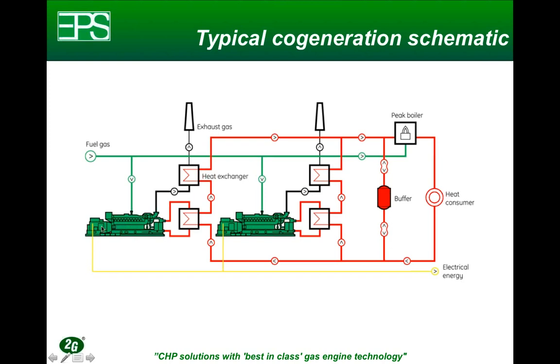Then when the engine is producing power, it will also produce heat, and it will have a few circuits on the engine where heat can be recovered. It would be from the engine jacket water, oil cooler, and intercooler. That's heat that typically is available in the form of hot water. And this loop here is where this hot water would be recovered from those circuits. Then there's also heat in the exhaust, and that heat can be in the form of hot water, but could also be in the form of steam and some other sources.